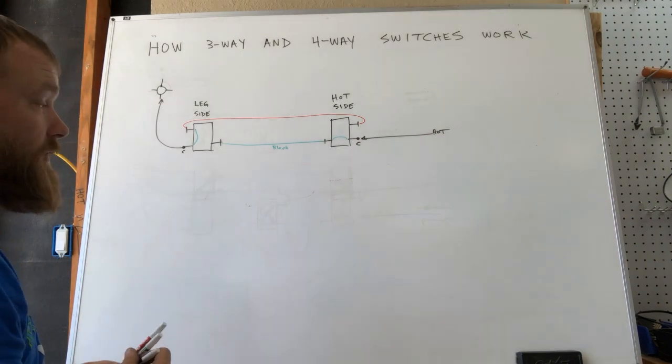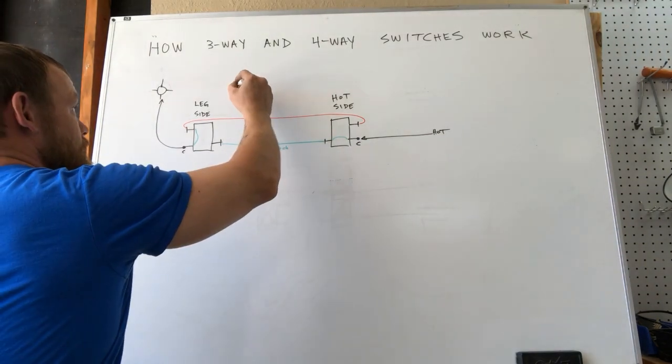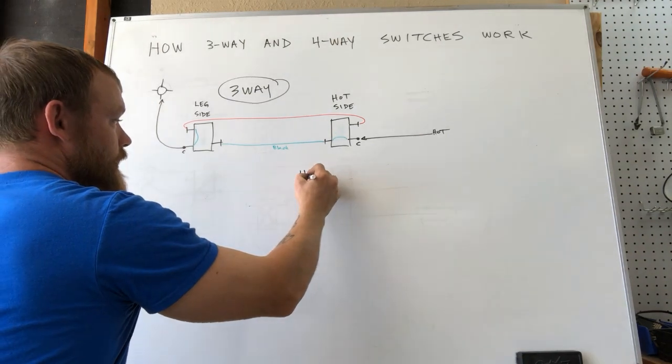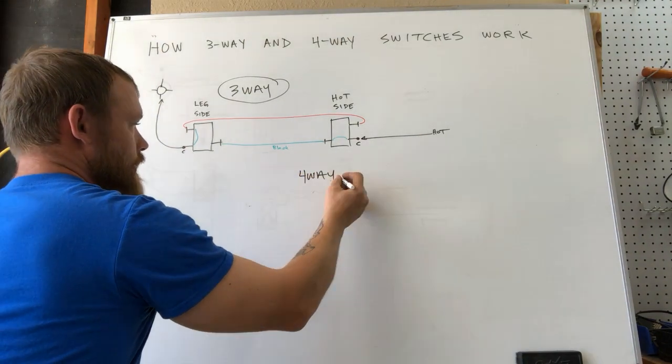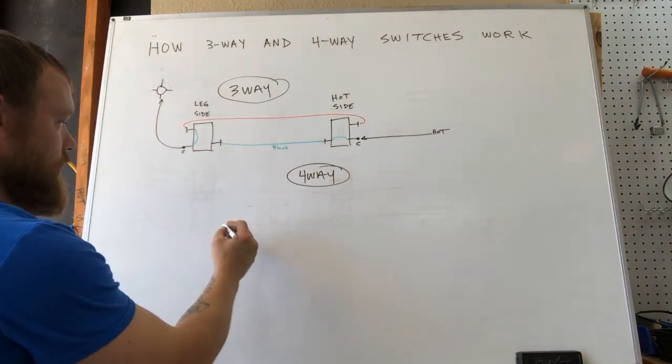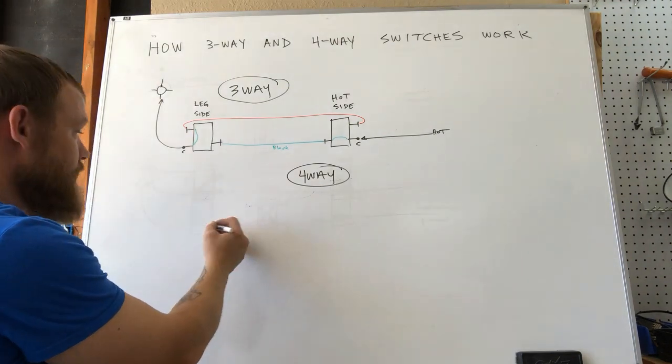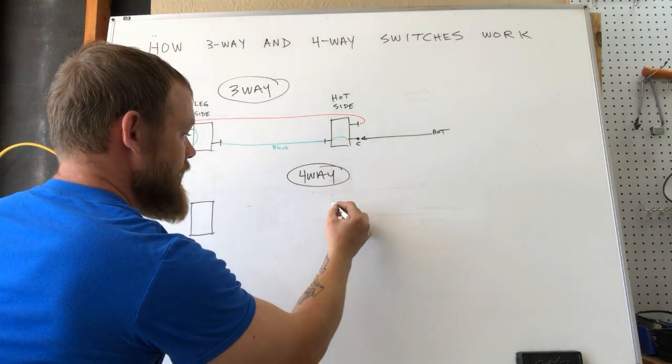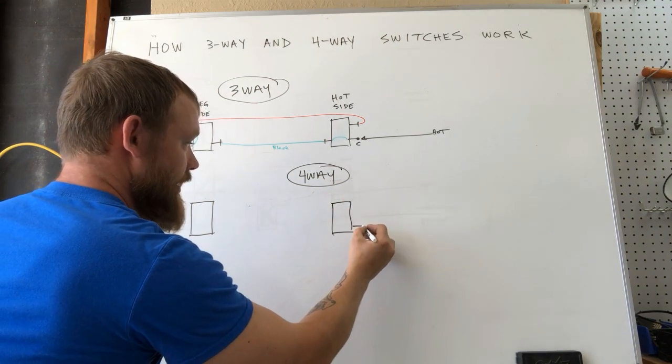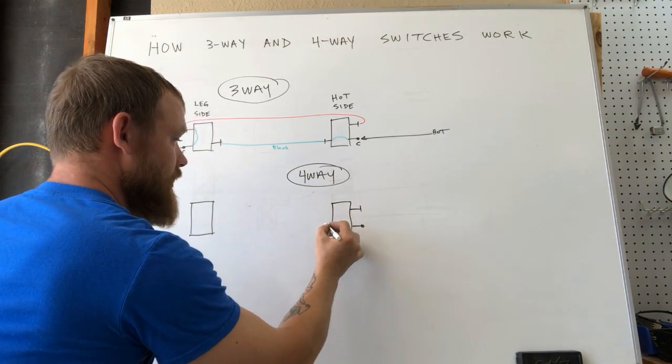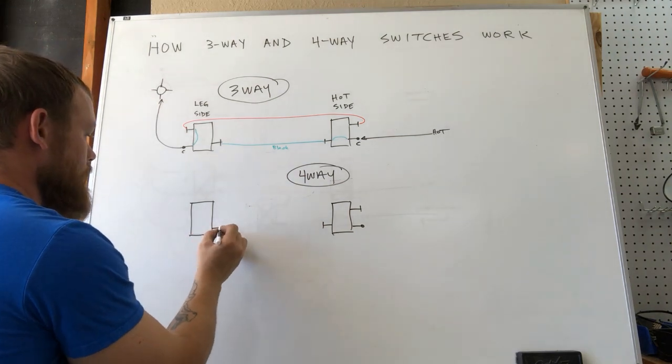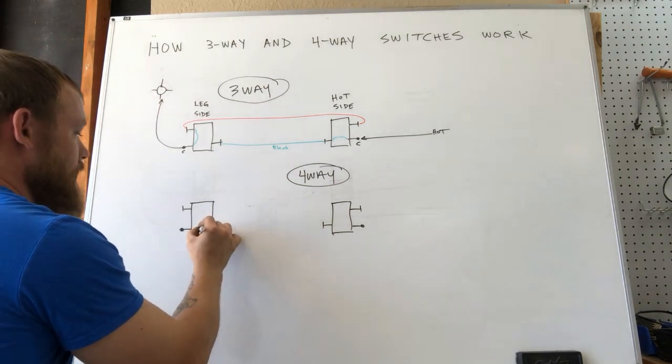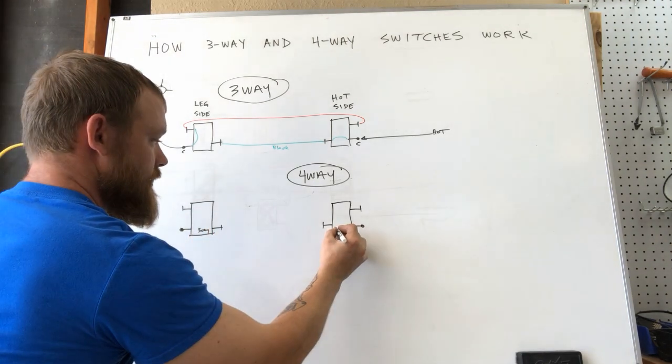So next is going to be our four-way. This is three-way. This is going to be four-way. So just like we're going to have on a three-way setup, you're going to have your two outside switches that are three-way switches. So you still have a common terminal, gold, gold. Over here you've got gold, gold, common. So this is a three-way. This is a three-way. And in the middle, you're going to have a four-way.